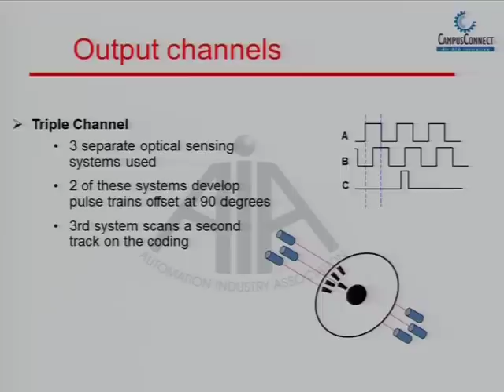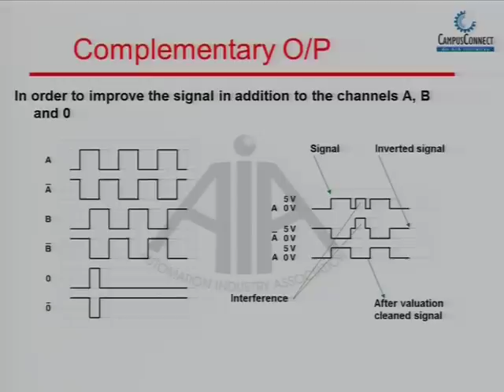So if you rotate an encoder and you have moved a distance of 10 mm and there is a power failure, you have to move in an anti-clockwise direction so that you can reach the C channel, the zero channel pulse or marker pulse, right? Which is not the case with absolute encoders. Again, since there is a possibility of noise interfering, each of these three channels has a complementary output. That means all three have opposite outputs. This helps to reduce the noise.